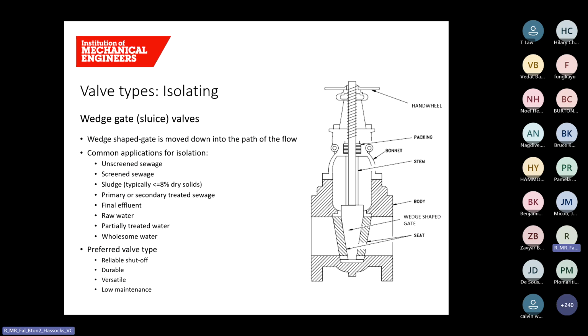Hi everyone. The first type of isolating valve I'll talk to you about today is the wedge gate valve, sometimes referred to as a sluice valve. The gate is wedge-shaped in design, and this provides a tight seal when closed. The gate itself moves in a linear motion, either up or down, in a straight line perpendicular to the flow. When fully open, it offers minimal flow resistance, allowing full bore unobstructed flow. The valve can also be used bidirectionally, allowing flow in either direction. It's operated either by manual means, by things such as hand wheels, or it can be actuated. Common applications for isolation cover everything from unscreened sewage right through to wholesome water and everything in between. These valves are extensively used in the water industry.